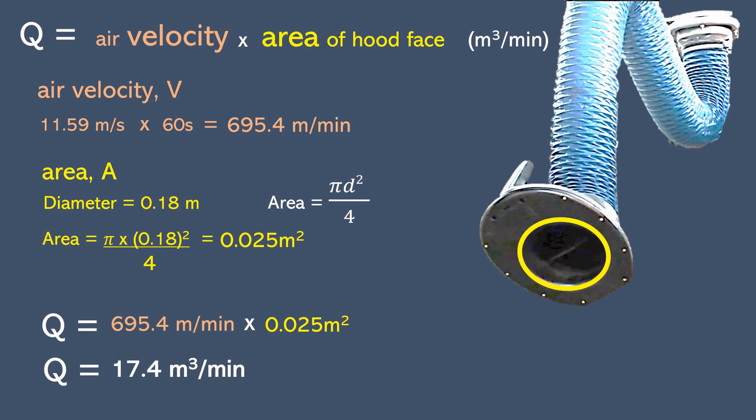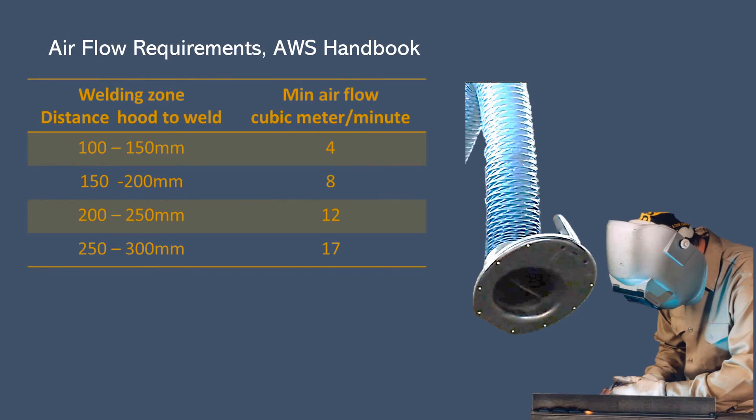Now that is how much air that goes into the LEV, aka the performance of the LEV itself. Now that we got the airflow, we can compare it to the airflow requirement from the AWS Handbook. Our LEV airflow is 17.4 cubic meter per minute. Thus, the suitable distance from the hood to the weld area is between 250 to 300 millimeters or about 1 foot.